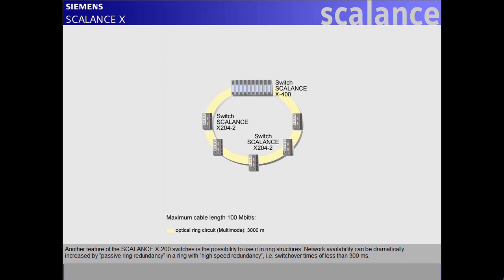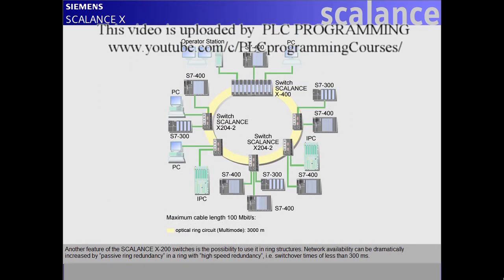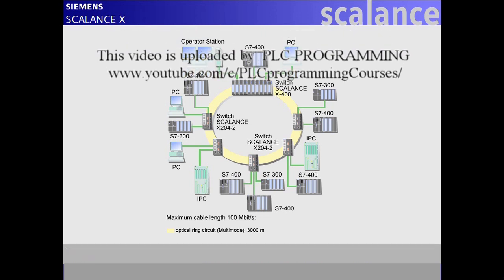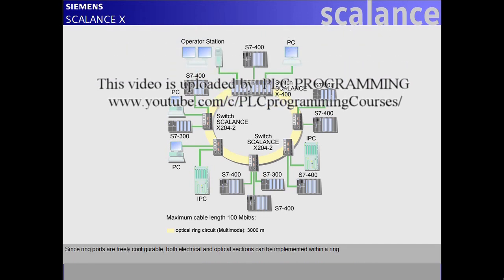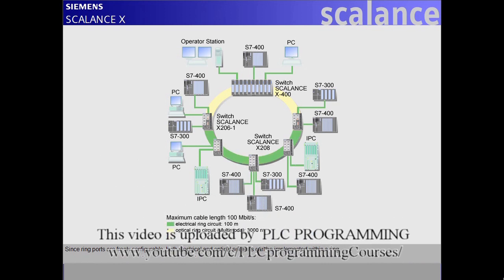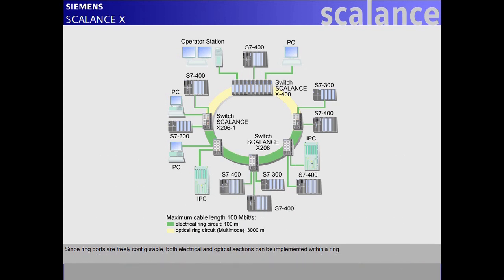Another feature of the Scalance X200 switches is the possibility to use them in ring structures. Network availability can be dramatically increased by passive ring redundancy with high-speed redundancy, i.e. switchover times of less than 300 milliseconds. Since ring ports are freely configurable, both electrical and optical sections can be implemented within a ring.